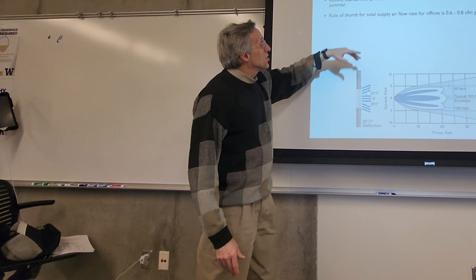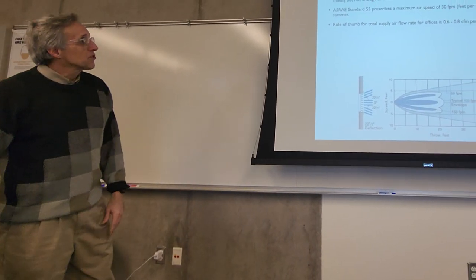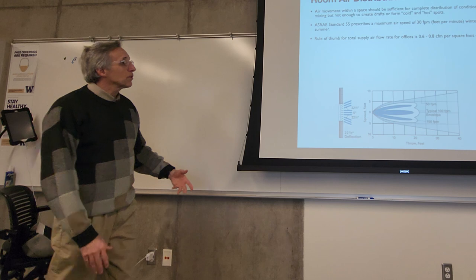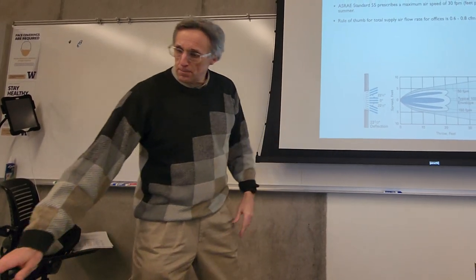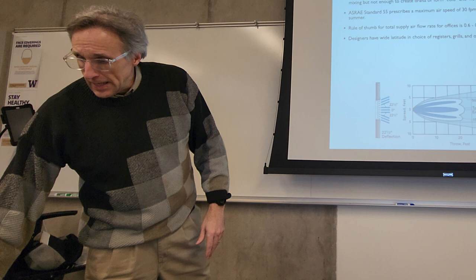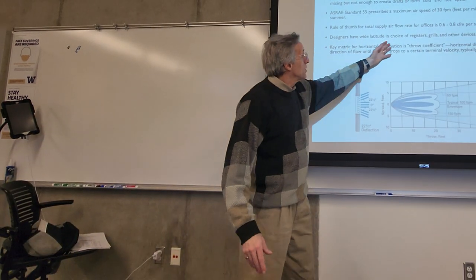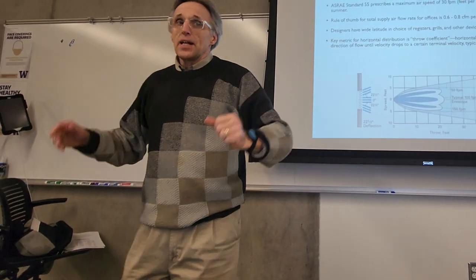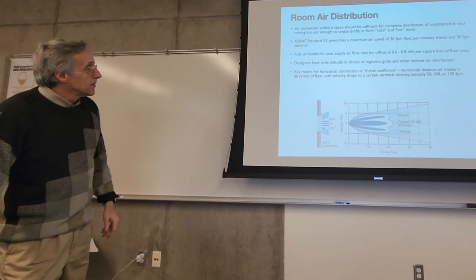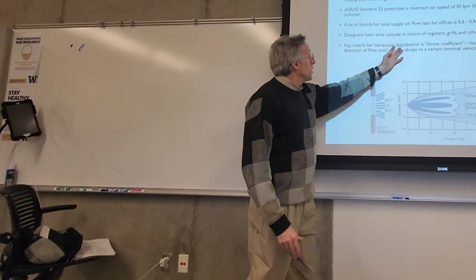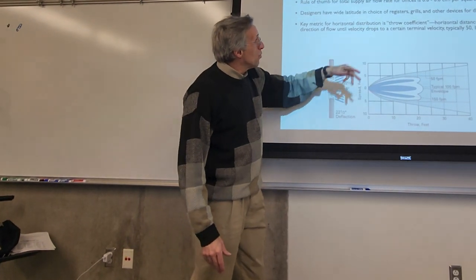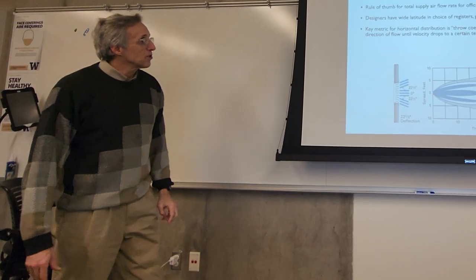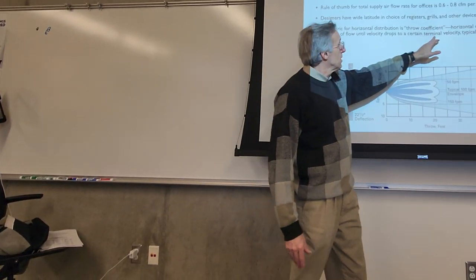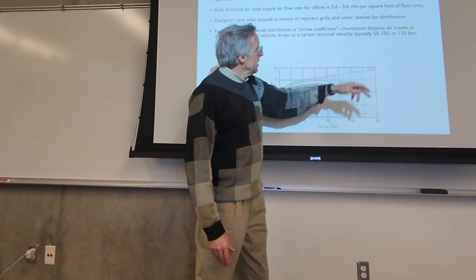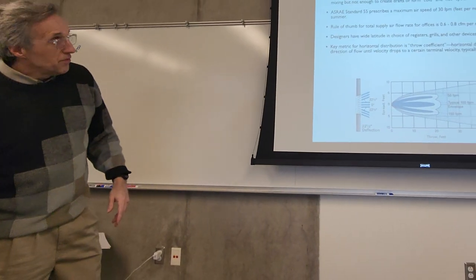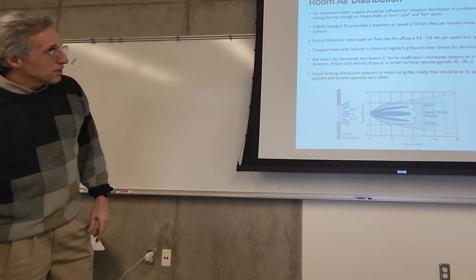Standard 55: max airspeed of 30 feet per minute in winter, 50 feet per minute in summer, total supply airflow rate for offices, just all these rules of thumb that we try to design with. And lots of different choices for registers and grills, and you get into aesthetics, what people like. And then a metric that we use when we're designing this part of the system is called the throw coefficient: the horizontal distance the air travels in the direction of flow until the velocity drops to terminal velocity. And 50 feet per minute is a common one to work with.